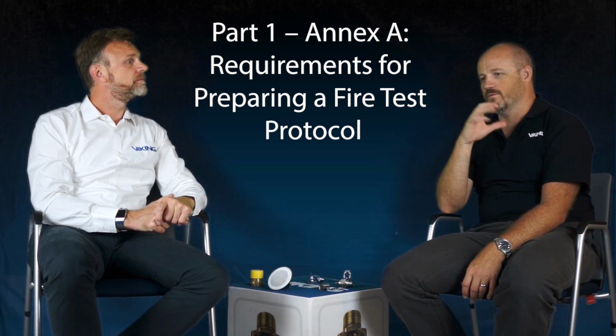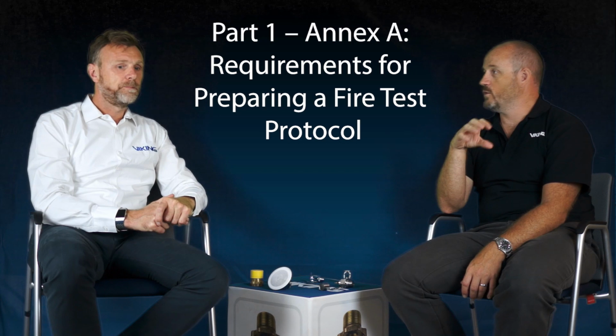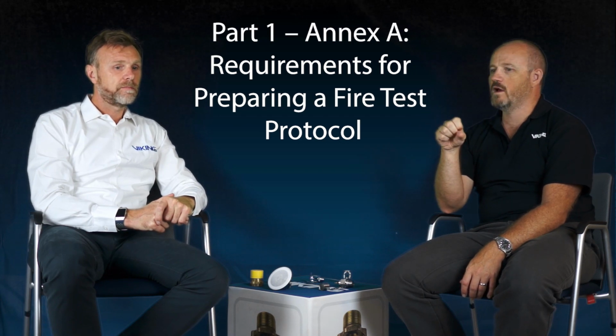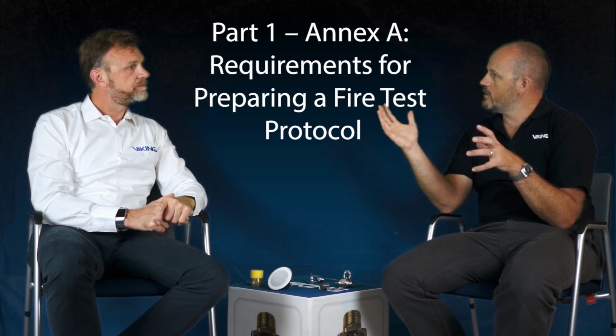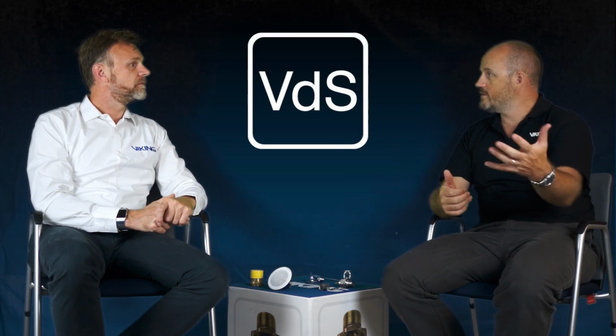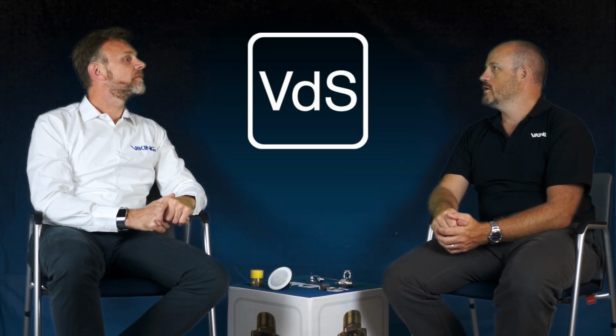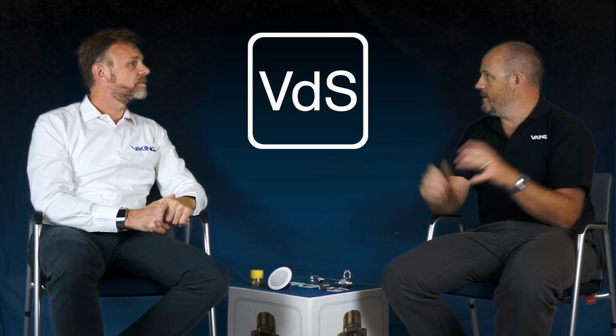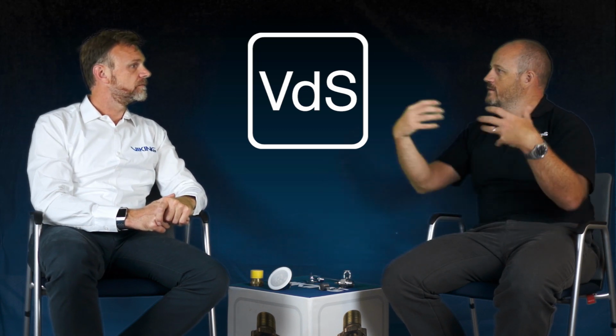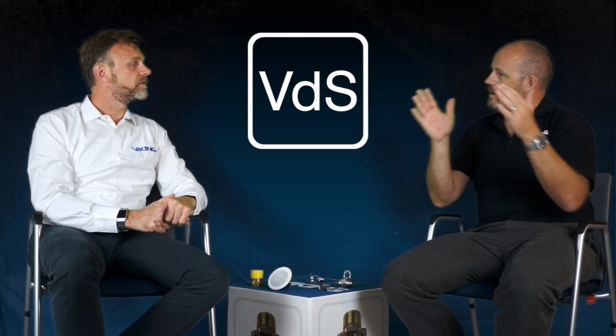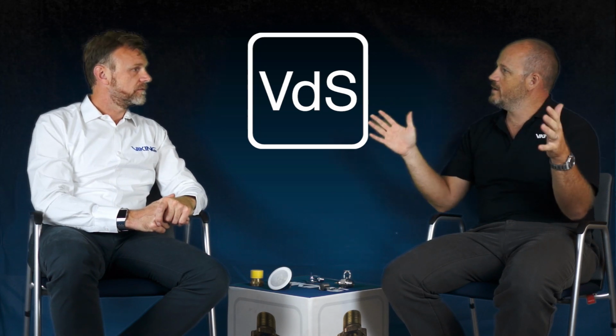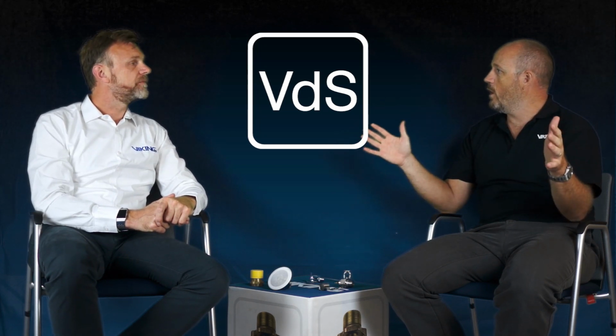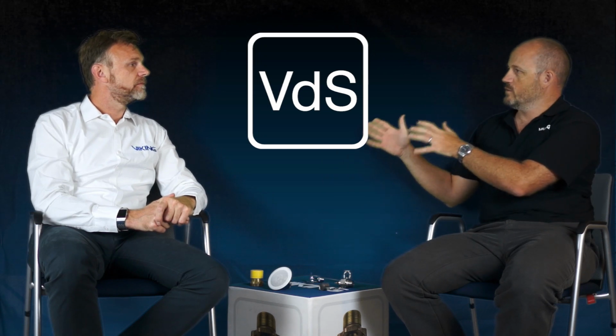And in our case, I'm very pleased to say that we've been working with VDS along these lines, looking with our Econ Aqua system at the testing that we have done. And really pleased to announce that we now have a VDS approval against EN 14972 Part 1 and this Annex A. That allows us to get the system out, and the market can see that it's fully in accordance with the body of Part 1, and that the fire testing was done in accordance with it.